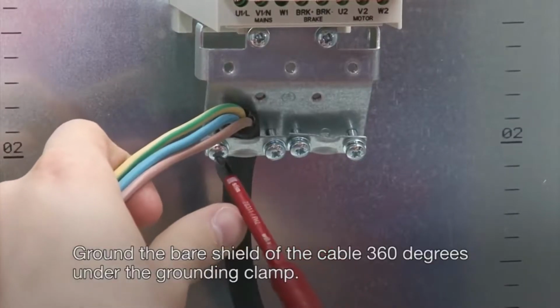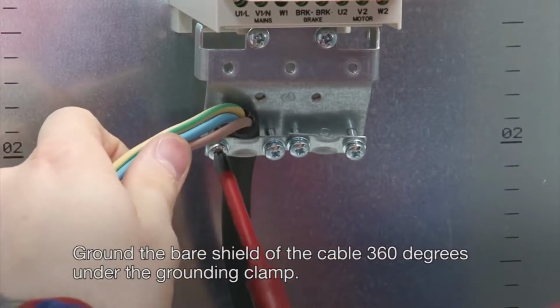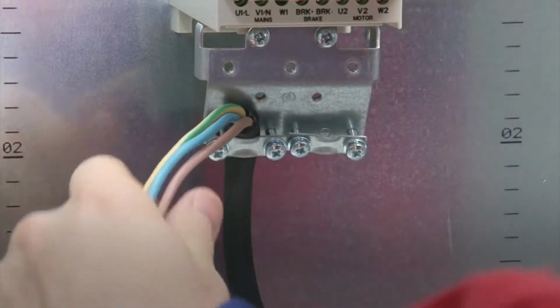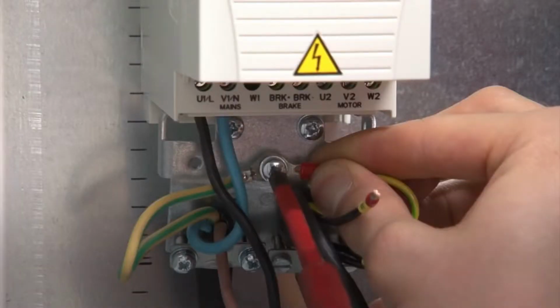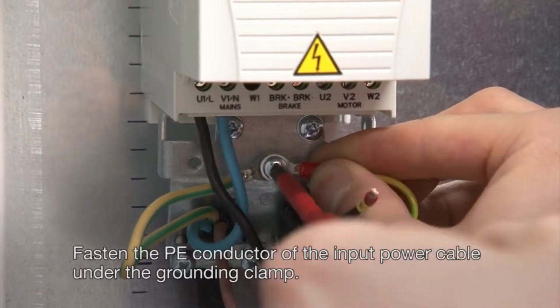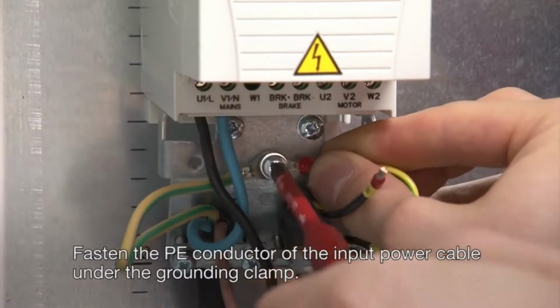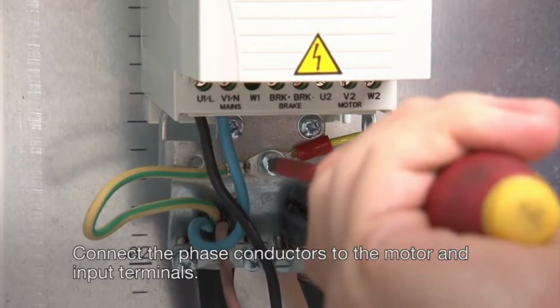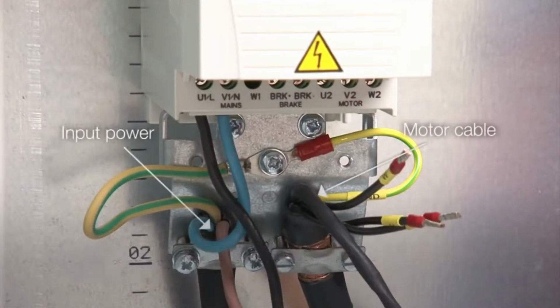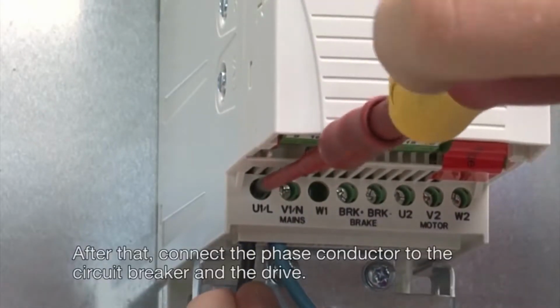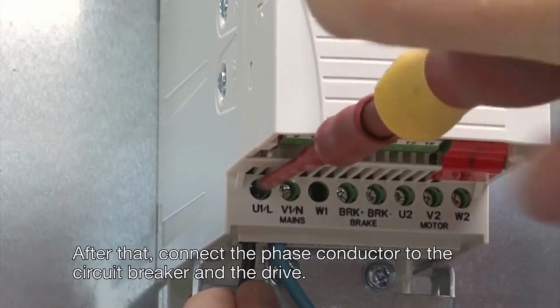Ground the bare shield of the cable 360 degrees under the grounding clamp. Fasten the PE conductor of the input power cable under the grounding clamp. Connect the phase conductors to the motor and input terminals. After that, connect the phase conductor to the circuit breaker and the drive.